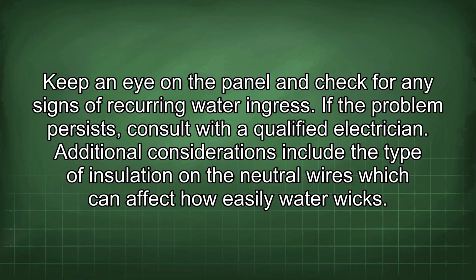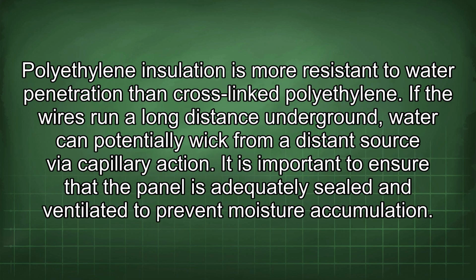Additional considerations include the type of insulation on the neutral wires, which can affect how easily water wicks. Polyethylene insulation is more resistant to water penetration than cross-linked polyethylene. If the wires run a long distance underground, water can potentially wick from a distant source via capillary action. It is important to ensure that the panel is adequately sealed and ventilated to prevent moisture accumulation.